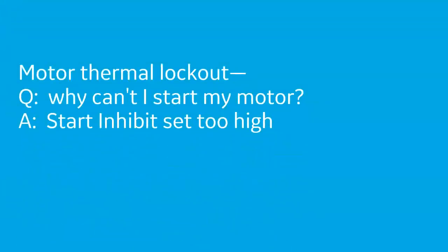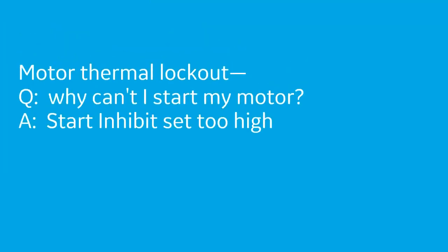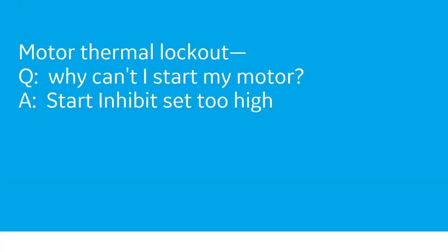So I feel like I'm running out of time, so I'm going to try to go through these a little quickly. But this was the question, why can't I start my motor? And the answer, the inhibit is set too high.